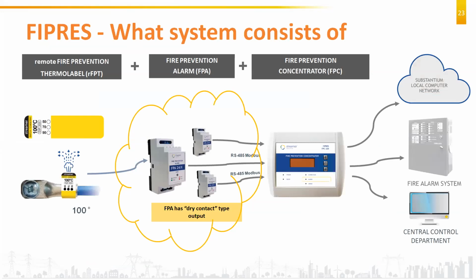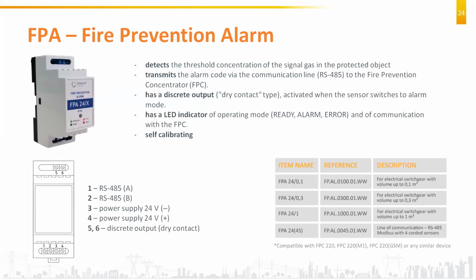Coming to the second component, which is FPA, fire prevention alarm. Okay. As explained, FPA will be installed in the same compartment in which the rFPTs are installed, and then it will detect the threshold concentration of the signal gas. Whenever it detects the gas, it will give an alarm via RS-485 communication. Secondly, it will give a discrete potential-free output which can be used for local annunciation. It has its own LED indicator which will flicker or become steady red in case of alarm. The RS-485 which is coming out of the FPA can be connected to your existing SCADA system, or it can be connected to a remote monitoring device, FPC.